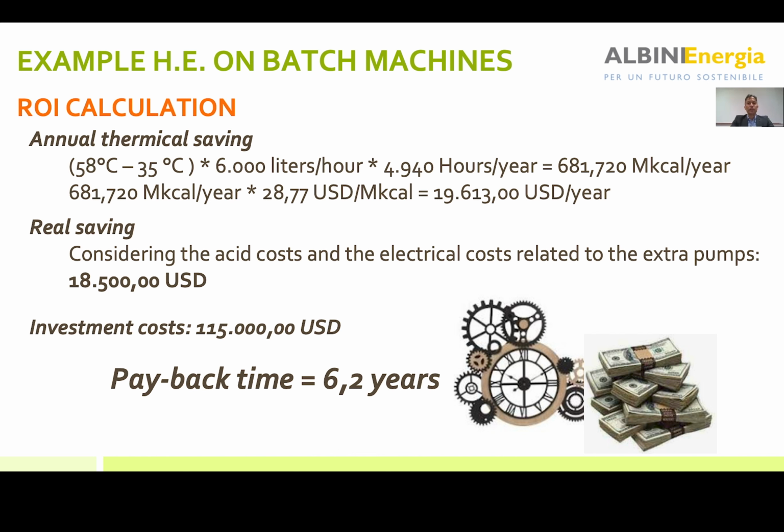Of course, this is a gross saving, because to be fair, you must reduce such cost considering the acid cost and the electrical cost related to the extra pumps that we have installed on our skid. So the final saving has been just 18,500 US dollar. The investment cost was almost 115,000 US dollar, everything included. It means also the installation cost, and so the payback time was 6.2 years.